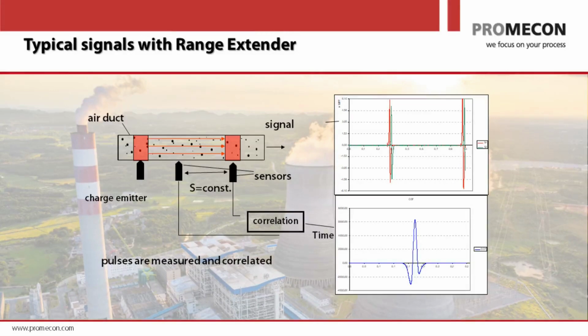And in big contrast to a delta P measurement, our measurement is strictly linear, right? So our measurement is linear from the top level to the lowest levels, which gives it a very big turn down ratio. And that's something that needs to be discussed a little bit more. If you have delta pressure readings, then it's very hard for you to measure the low range accurately. Because if you, for example, go down to 10% of your max flow, you are talking about 1% of your max pressure, right? And that really gets into a very, very small pressure measurement range. So DP measurements will show you all sorts of readings. Sometimes they will even show you negative readings. Because in this very low flow range, your pressure is almost 0.